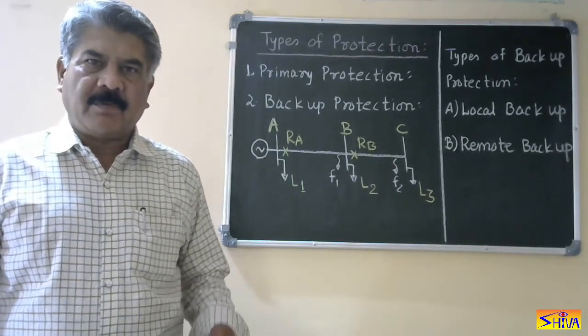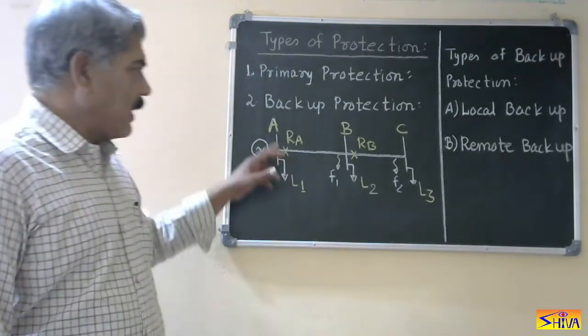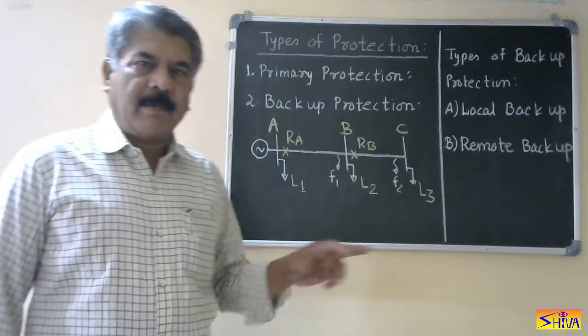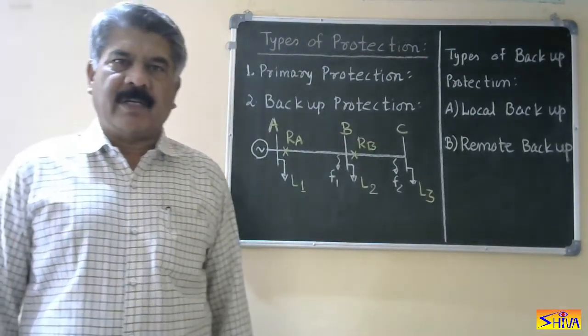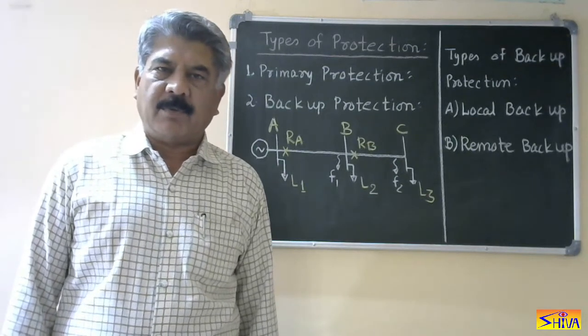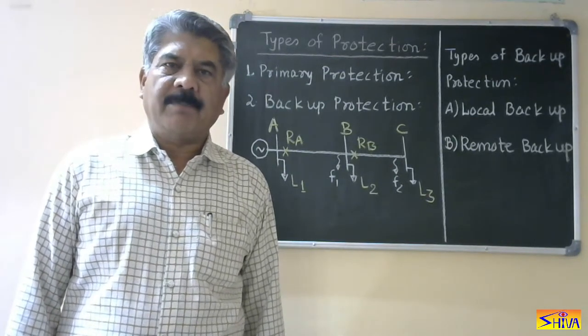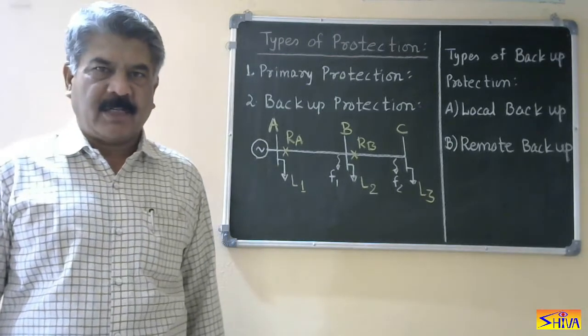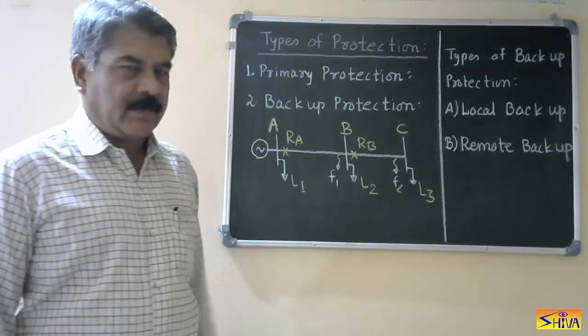Therefore we require a second line of protection — that is called backup protection. Backup protection is nothing but the second line of protection, and it operates when primary protection fails to operate or when primary protection is taken out for maintenance purposes.